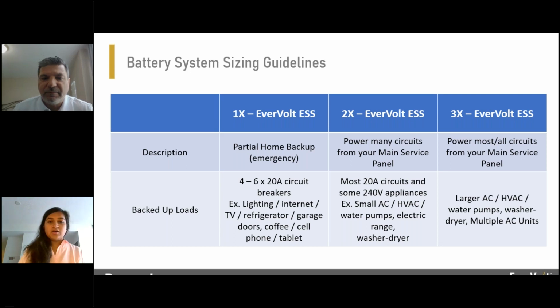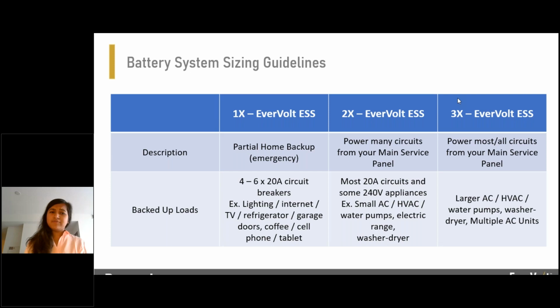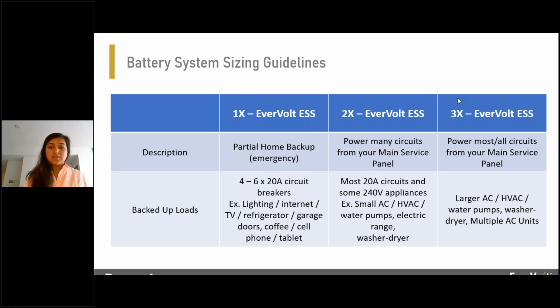Thanks, Tony. With our storage system offering, a single Evervolt system has an output power of 5.5 kilowatts of AC. The sizing guideline that we have built is a rule of thumb to follow when applying these designs for specific applications. Most customers want backed up loads, using the energy storage system in case of an outage, required to back up critical loads such as lighting, internet, refrigerators, and garage doors, which can be achieved with a single system. However, if the homeowner wants to back up more appliances, then we would be required to stack additional systems as well. With 2 systems, we can back up some additional electric pumps and inductive loads such as ACs and HVAC appliances, as well as some more 20 amp circuits.